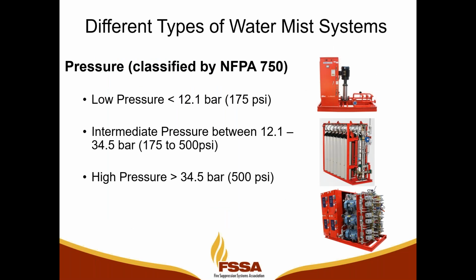So there are different types of water mist systems that are out there, and these are all classified by NFPA 750. So you have low pressure water mist systems, which typically are under 175 psi in working pressure. Intermediate pressure is 175 to 500 psi in working pressure. And then high pressure is anything over 500 psi. Next slide.